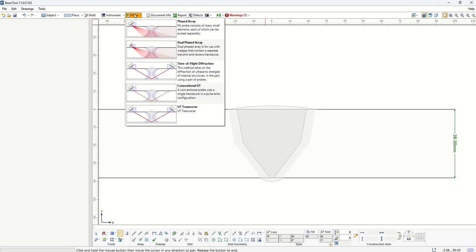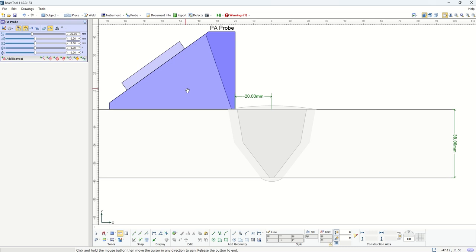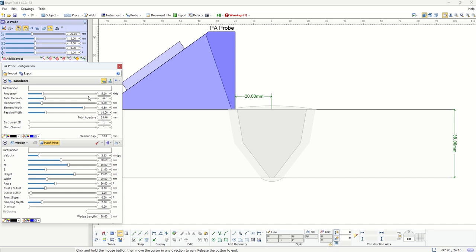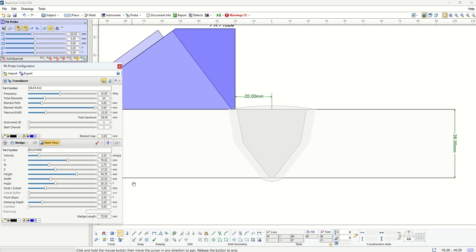Again, because FMC, full matrix capture, is an inspection technique that requires a phased array probe, the probe would be phased array. And for us to have a highly sensitive technique, we want to use a large aperture probe and high frequency. So here, my choice would be 10L64A12, which is a 10 megahertz probe, 64 elements, and 0.6 pitch. And I'm going to use the SA12N55S wedge that basically goes with that for creating a shear beam into the piece.